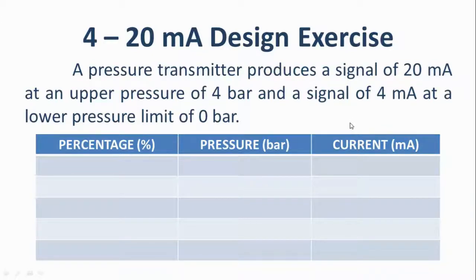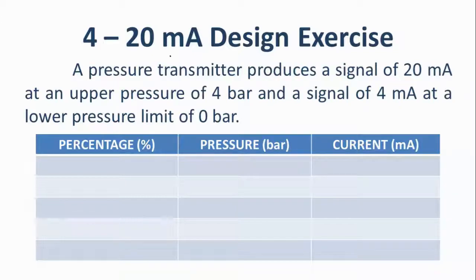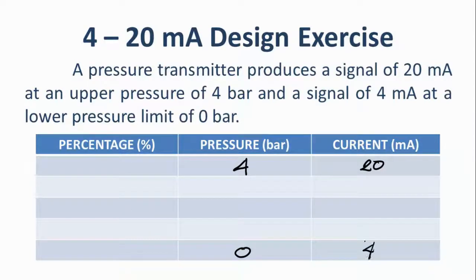From the problem statement, the pressure transmitter produces a signal of 20 mA at the upper pressure limit, so we write 20 mA at 4 bar. At the lower pressure limit of 0 bar, the output is 4 mA. So we enter 0 bar with 4 mA as our lower boundary values.